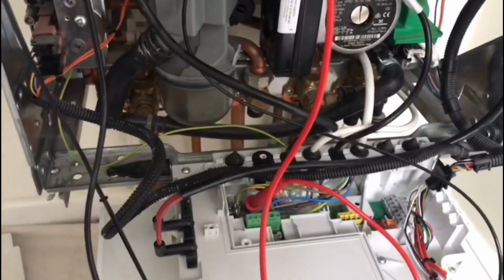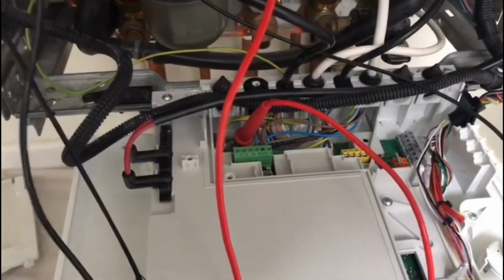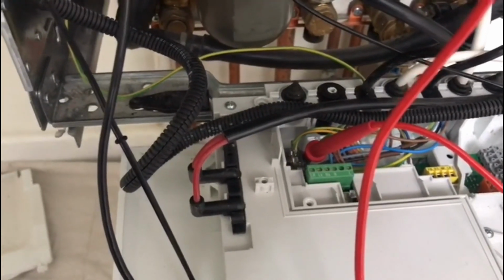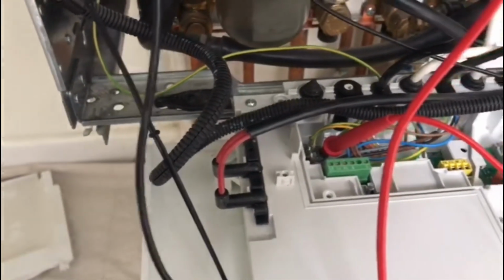Next test will be a resistance to earth test, which is testing between live and earth. Now you certainly don't want continuity on this test, because continuity between live and earth would be a live to earth fault. It would trip out, and should hopefully blow your 3 amp fuse. If not, it should blow the fast blow fuse in your circuit board, which is this little fuse just there. That's your fast blow fuse. So if there's any fault, it would hopefully blow that fuse, and if not, your 3 amp system fuse, stopping any electrical damage to your boiler.